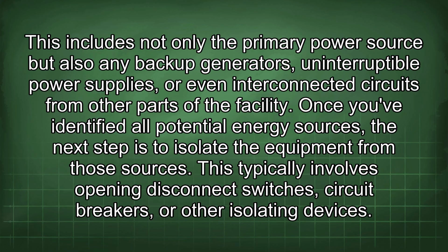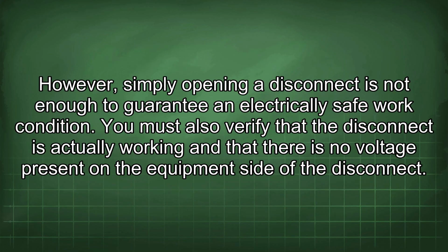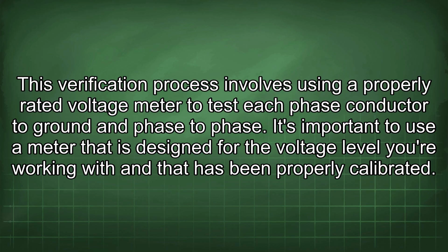Once you've identified all potential energy sources, the next step is to isolate the equipment from those sources. This typically involves opening disconnect switches, circuit breakers, or other isolating devices. However, simply opening a disconnect is not enough to guarantee an electrically safe work condition. You must also verify that the disconnect is actually working and that there is no voltage present on the equipment side of the disconnect. This verification process involves using a properly rated voltage meter to test each phase conductor to ground and phase to phase.